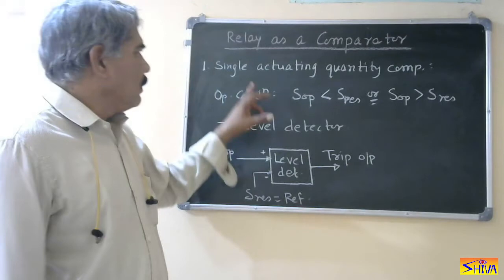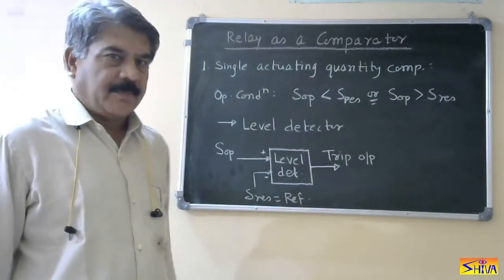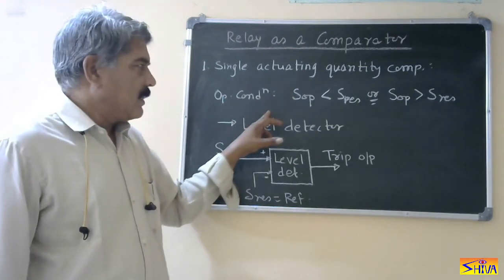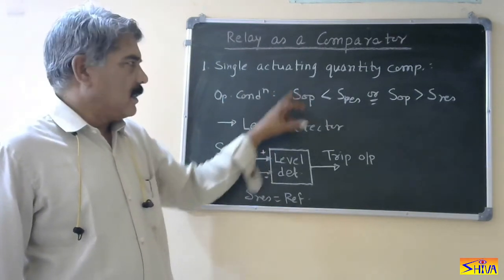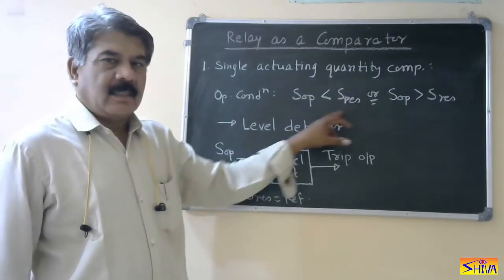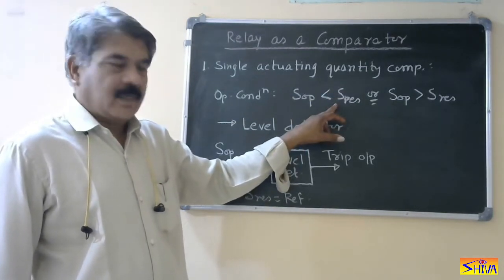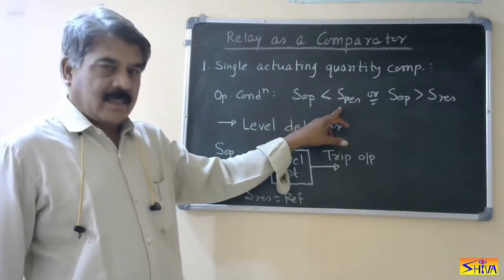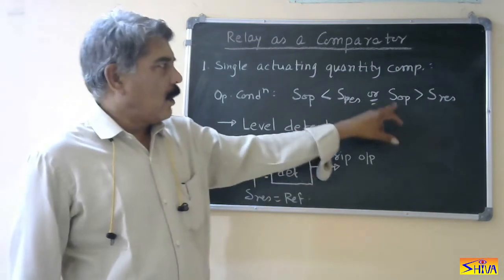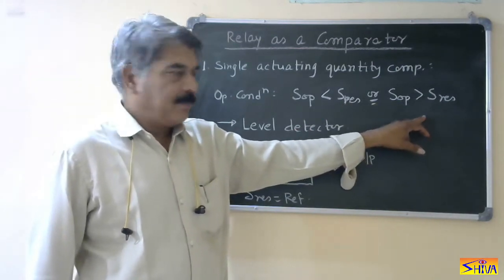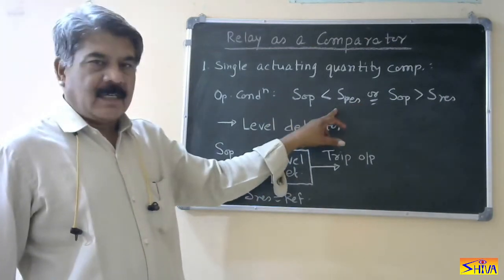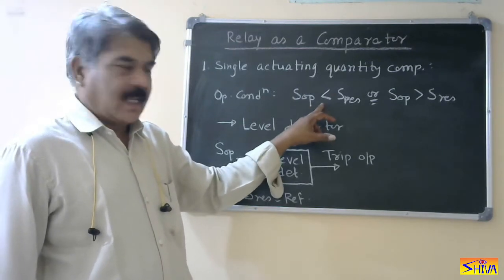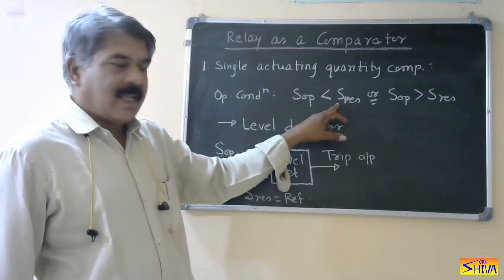Let us start with the comparator with single actuating quantity. In this single actuating quantity comparator, the operating condition involves S-operating, the operating quantity, and a restoring or reference quantity. The operating condition may be: operating quantity less than restoring quantity, or operating quantity greater than the restoring quantity. If we consider the first condition, it may be an undervoltage or undercurrent type, because the operating quantity is less than the restoring quantity.